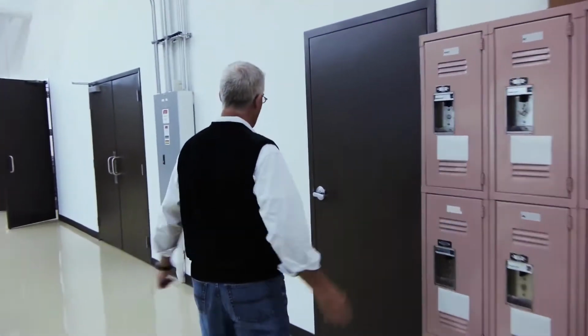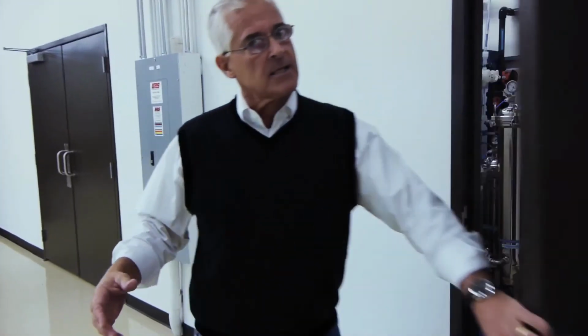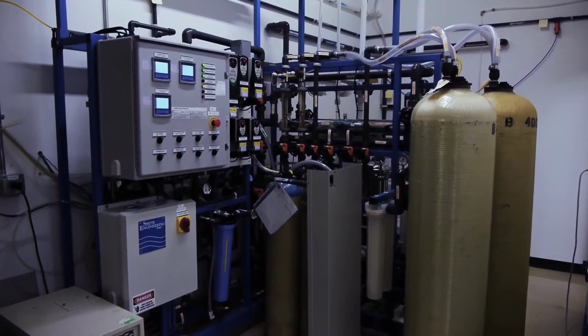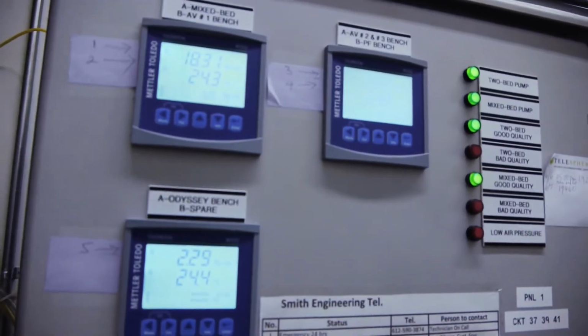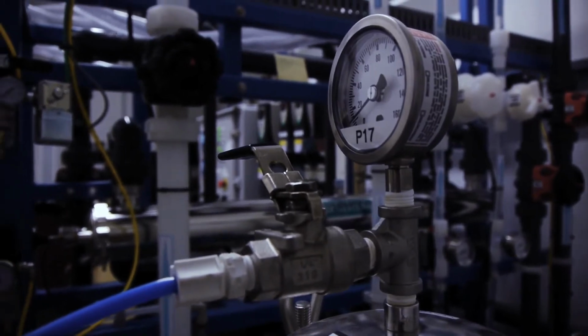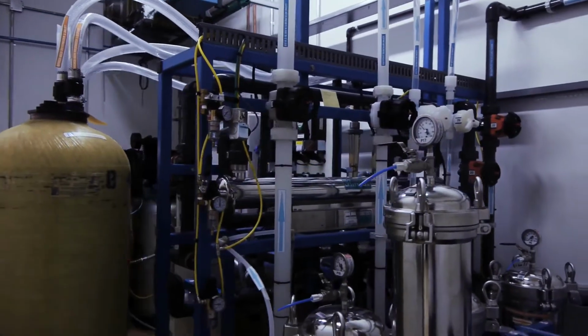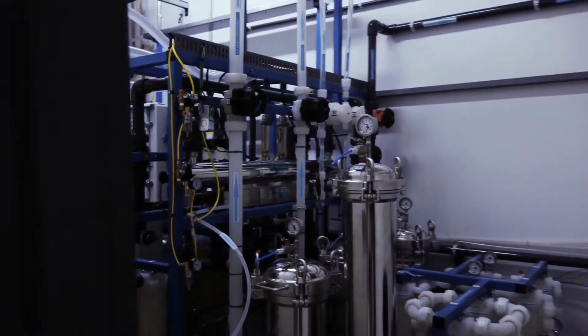Our facility's DI water system has a lot greater capacity, 65 gallons per minute, up to almost 250 liters per minute, so it can handle multiple high performance or high flow products at the same time.